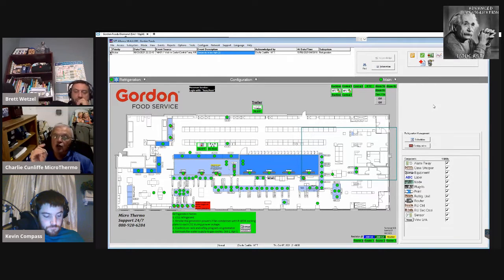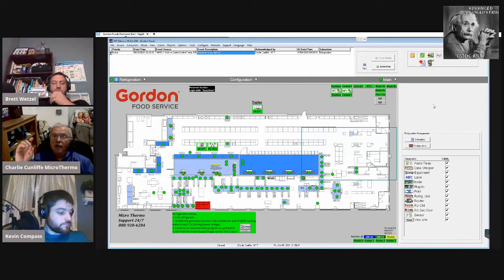They have to land directly to that board. We don't want to take it as a network broadcast, because no matter how fast the network is, there's still a lag time when it's a broadcast variable rather than a pressure transducer wired directly to the board. I want to make sure everybody listening to the podcast knows that when it comes to controlling a rack, especially a CO2 rack.